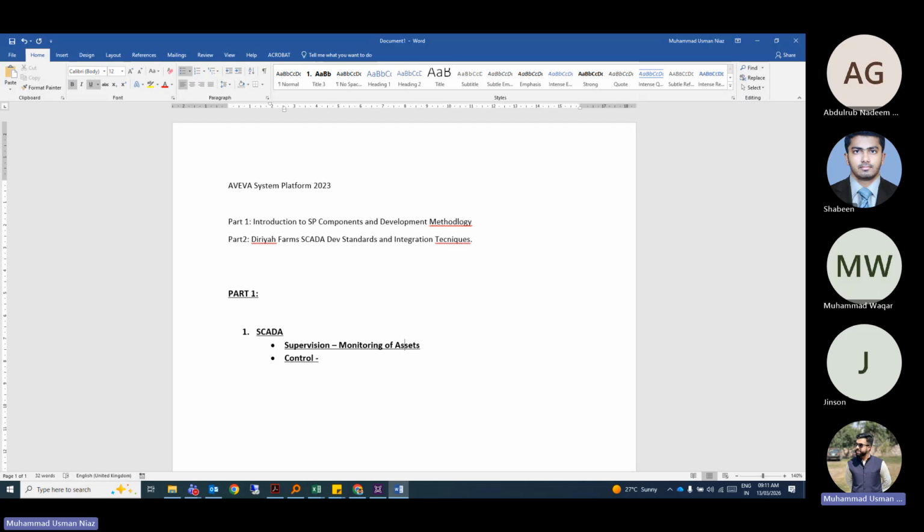So apart from giving control for each and every component separately, in SCADA we can design some response plans as well. For example, in case of fire, using the capability of scripting in SCADA, we can give control commands to each and every component to work in unison and do one complete task in case of fire. So control of assets is the second component, and the third and the most distinguishing feature of SCADA as compared to HMIs is data acquisition.